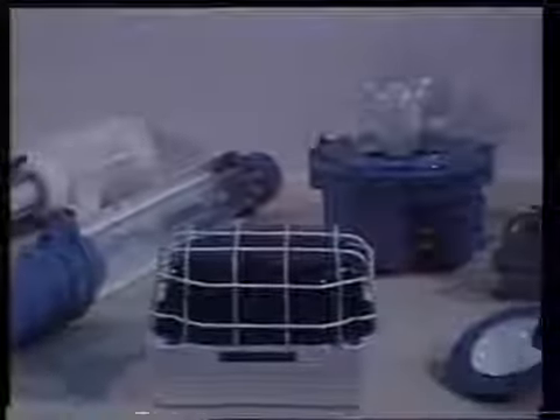There is a whole range of fittings, weatherproof, explosion-proof, or both, which are used in hazardous areas, some of which are seen here. The essential thing to remember is that the flanges of the weatherproof fittings normally hold a weatherproof gasket between them. But the explosion or flame-proof fittings must have a flame path clear between the flanges without gaskets or paint obstructing it. Some lighting applications provide very large areas with a prescribed light level, 50 lux for instance, for safe cargo working at night on deck areas.